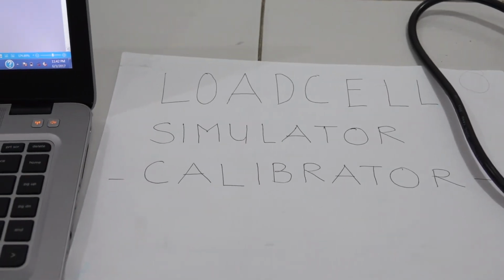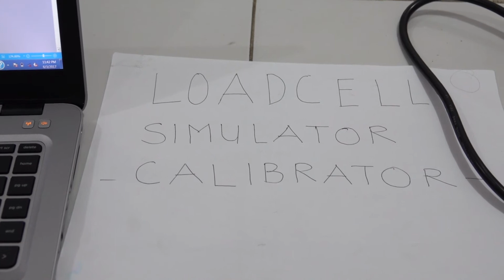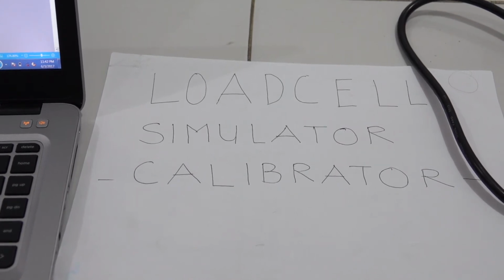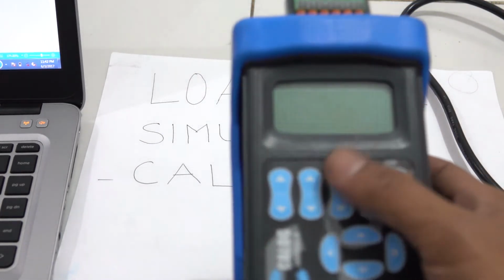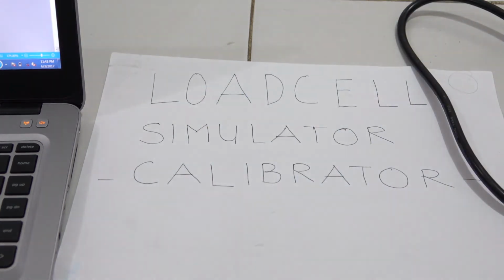Okay, just as a background of this video here, why do we need this load cell simulator or calibrator? Of course, the first thing in your mind is that we need this to calibrate the reading of the load cell indicator, to see how consistent the reading is. If you increase the voltage or millivolts of these load cells, what is the correlation between the millivolt output from the load cell and the reading from the load cell indicators?